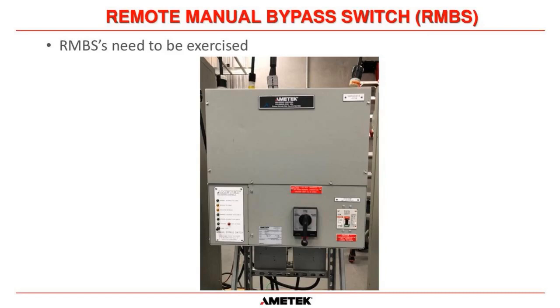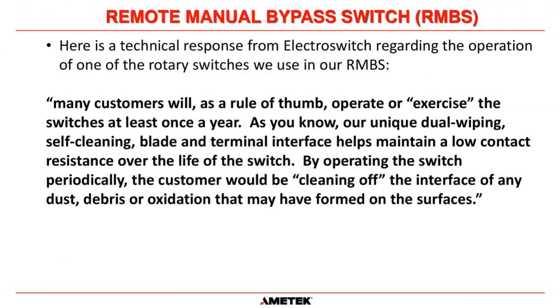And we have found in many circumstances that plants that don't operate their maintenance bypass switch on a regular basis can have issues. We have found many, many times that if we go to a UPS that hasn't had the maintenance bypass switch operated for maybe 5-10 years, sometimes that switch will not even move. It will not allow us to put that system into bypass.